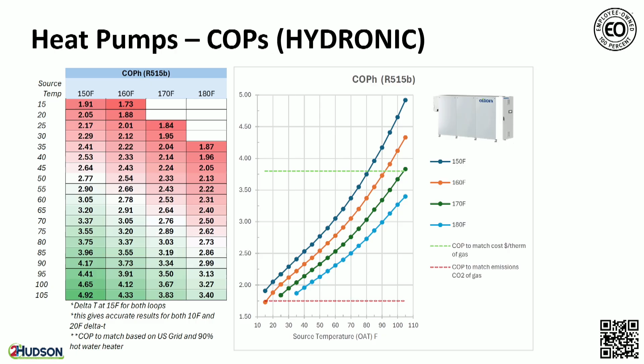with this equipment. That being said, COPs are instantaneous ratings and factory conditions. It is important in these design considerations to take a nuanced approach into what the annual loading for a building will be like. What can I do to design the system that will change those effective COPs to fit my condition? So I would heavily encourage anything like a seasonal COP or different conditions when you're talking to your equipment manufacturers on what they are giving you. The brochure COP is not what you will see throughout a year of operation.